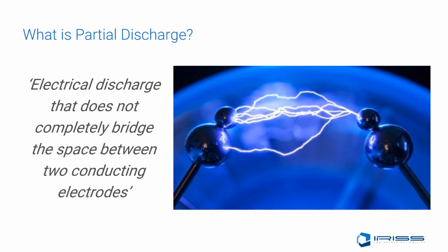Partial discharge may be found in liquid-filled transformers where the paper insulation starts to degrade with exposure to high heat levels. This will lead to the oil losing its insulation value and the degradation of the cellulose paper becomes more rampant. This produces bubbles in the oil, which allows the conduction of current inside of the equipment, which in turn will show up as TEV, AE, HFCT, or UHF indications.